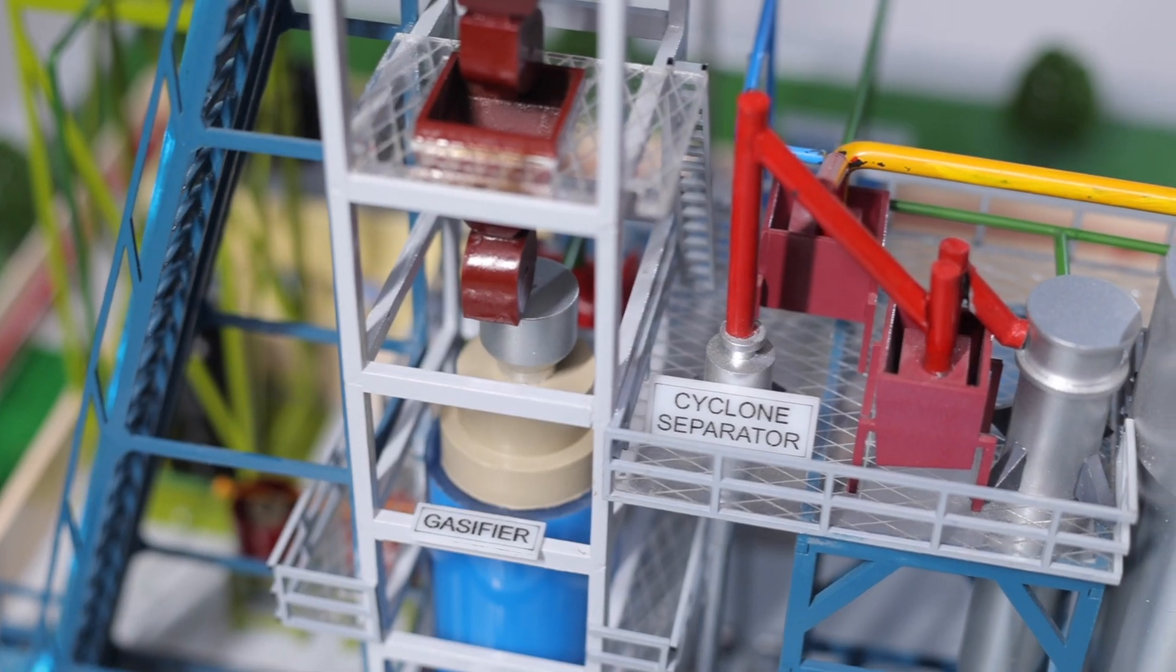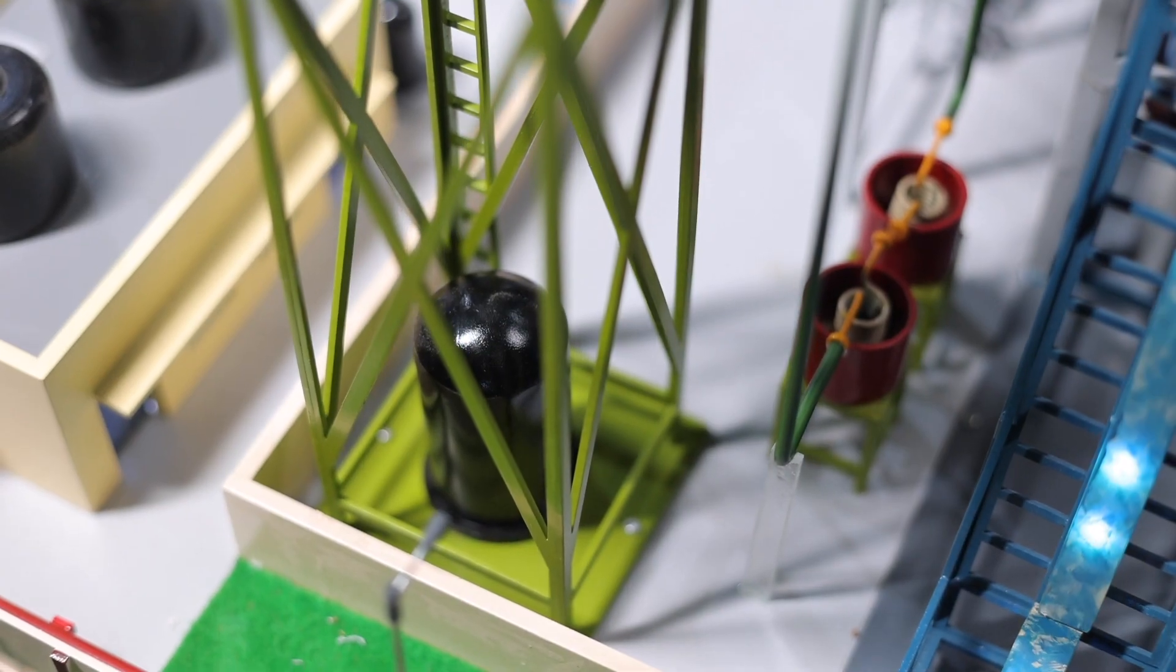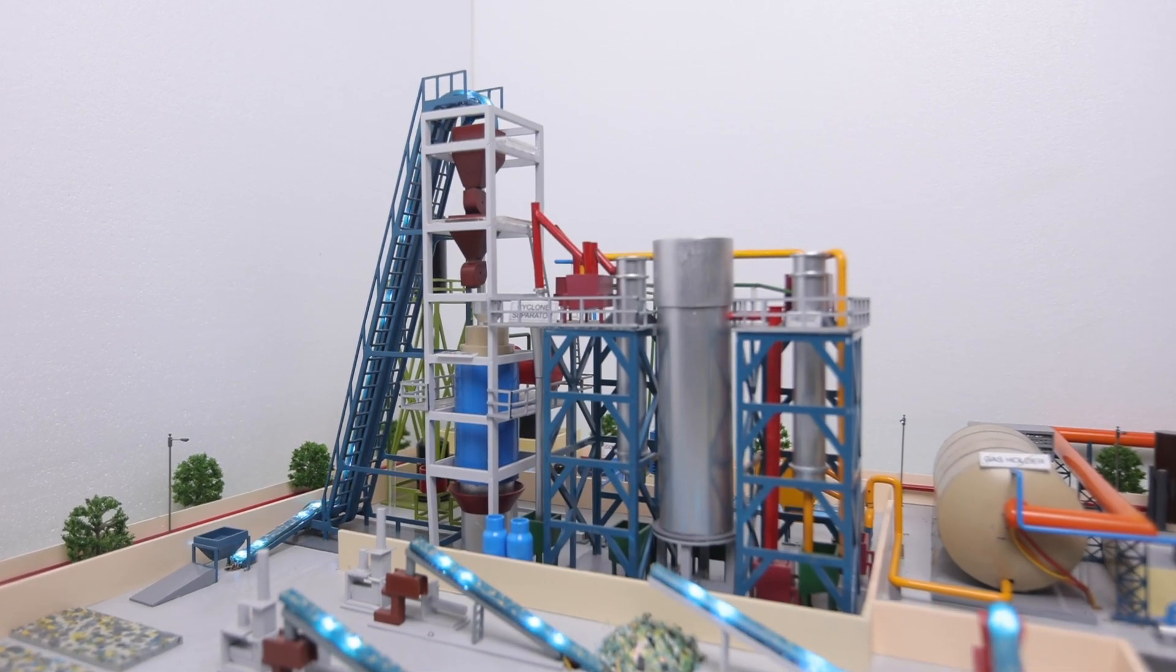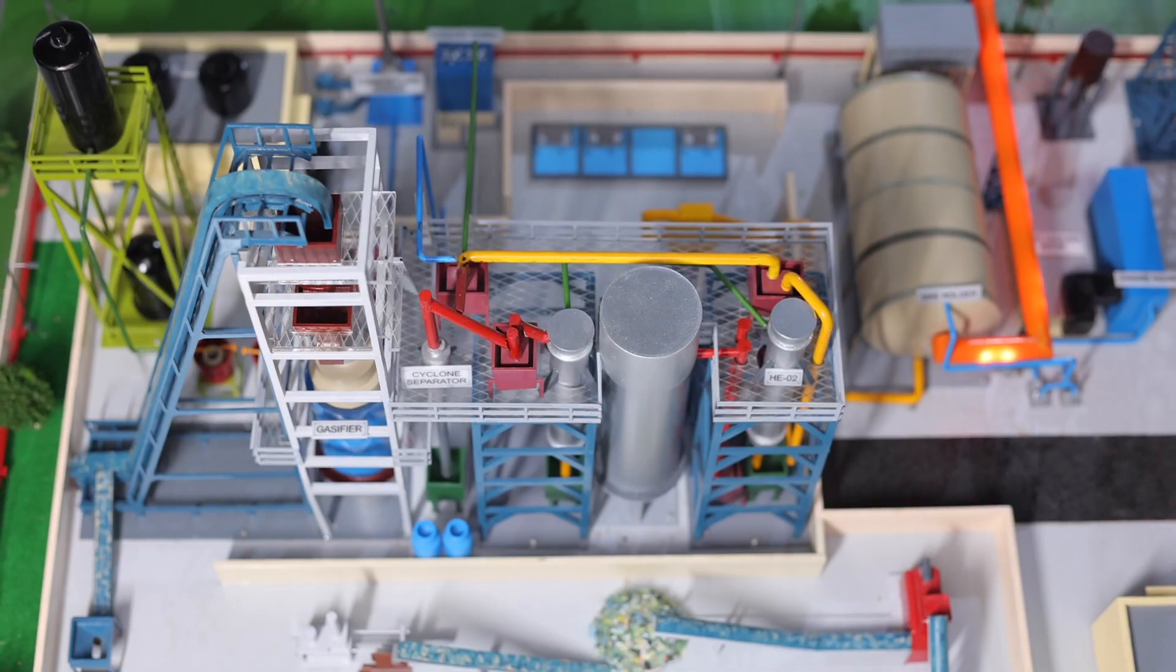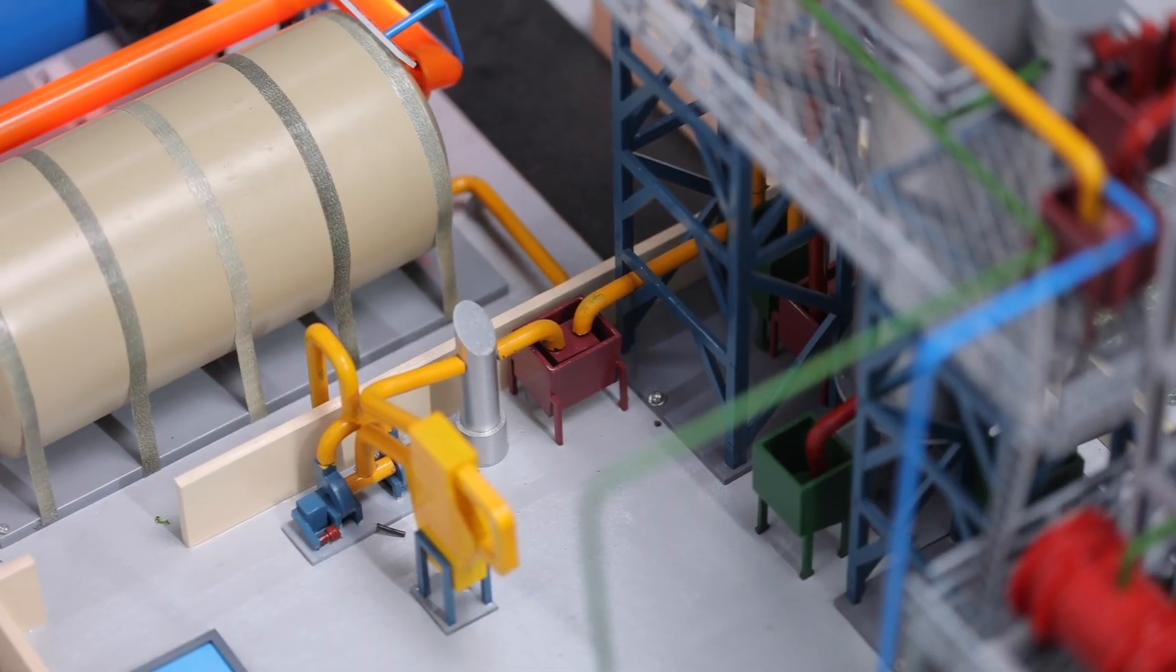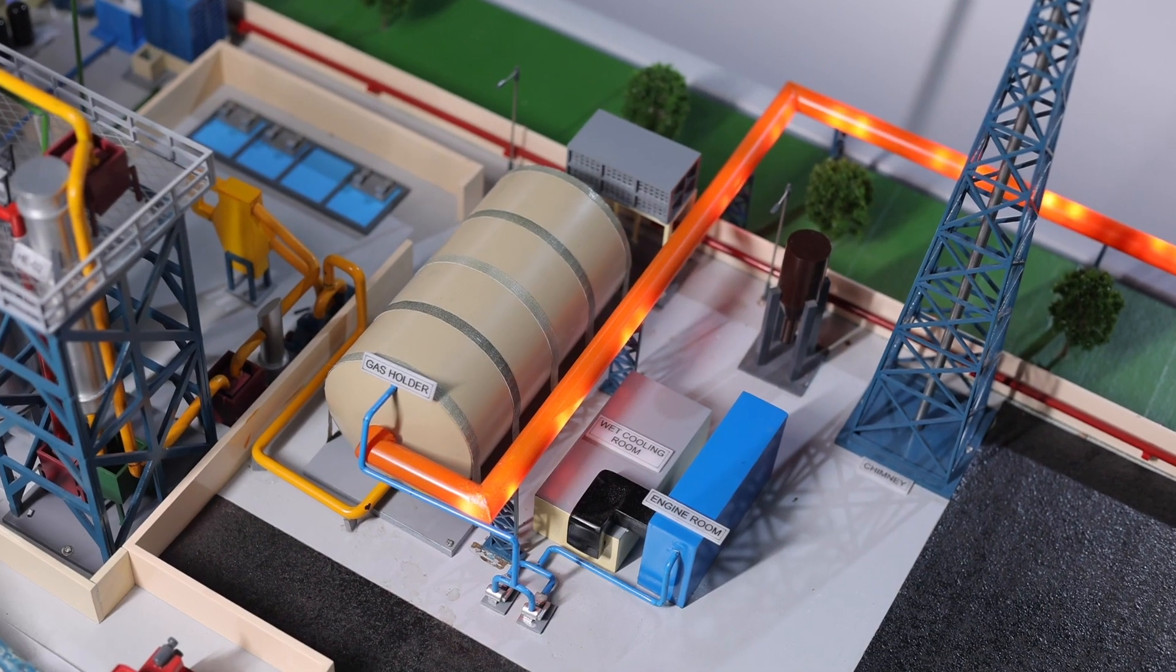Producer gas coming out from the gasifier will carry fuel dust particles. These dust particles are separated in a cyclone separator and gas is sent to the cleaning section for tar removal. Water vapor, tar and phenolic compounds are generated in the gasification process and separated in the gas cleaning section. The producer gas is passed through different cleaning and cooling sections before collecting into the gas holder.